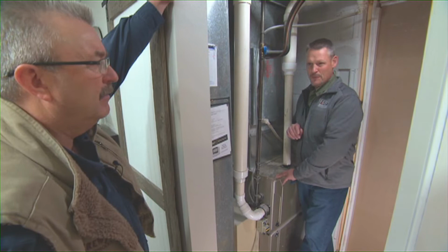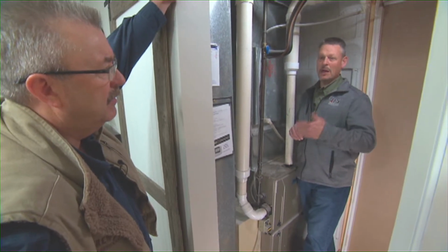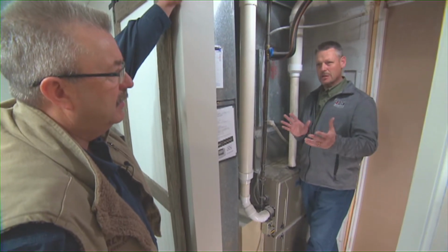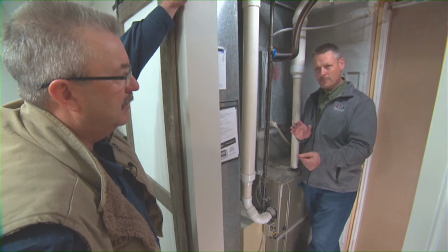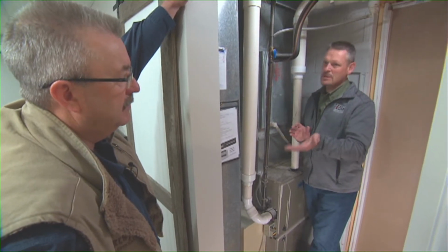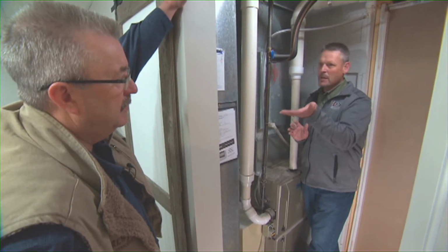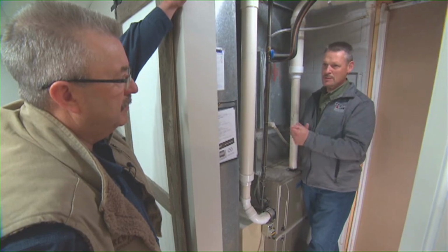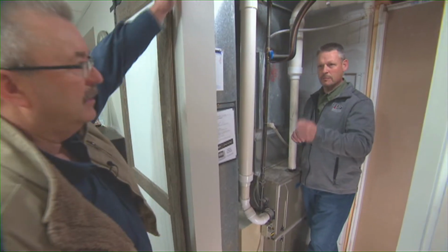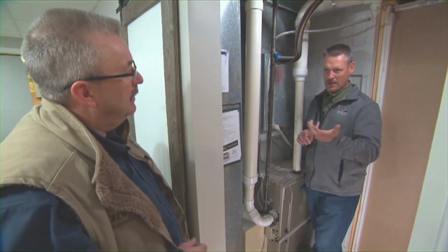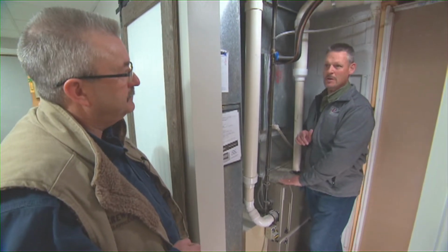This is a single stage furnace, so in the spring and fall, what'll happen is it puts out so much heat, it takes care of the heat load very rapidly. That's good in one sense, the house stays warmer. The bad part is it's short cycling the furnace, which isn't good. It's like you turn a light switch on and off multiple times, your bulb's gonna burn out faster. It puts added wear and tear on the furnace.